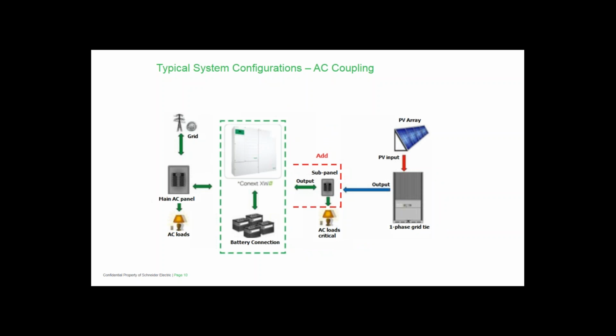When AC coupling, we are merely inserting the XW Plus or Conext SW into an existing system. All we are doing is dedicating a breaker in the main panel to the input of the battery-based system. Then we're adding a subpanel to dedicate the critical loads. This allows the battery-based inverter to fool the grid tie inverter into thinking the grid is still present, allowing PV production even when the grid is down. Now let's talk about monitoring.